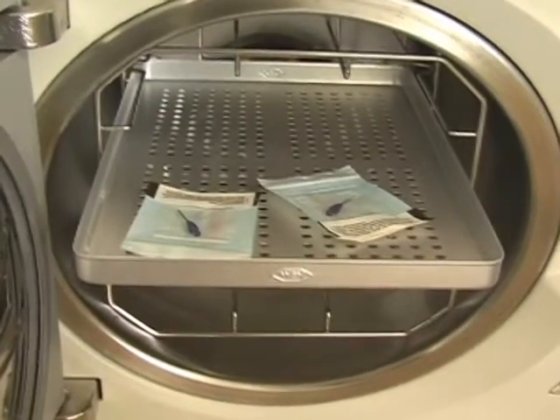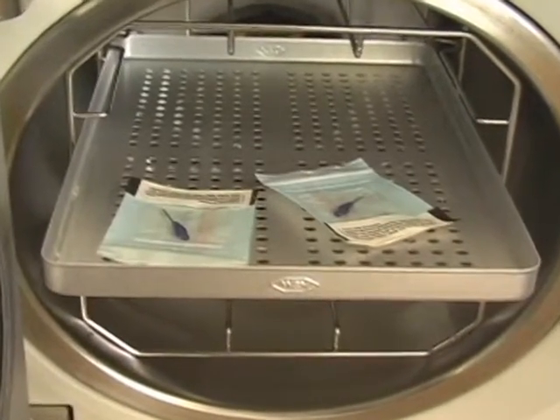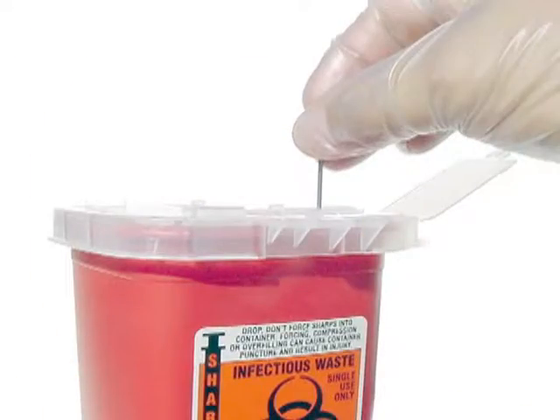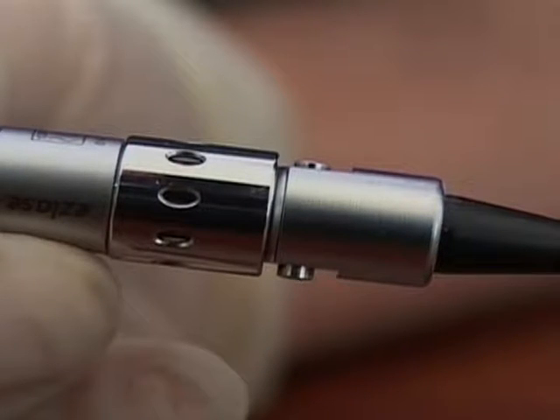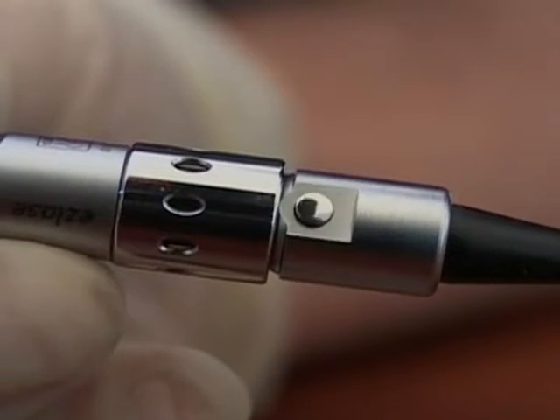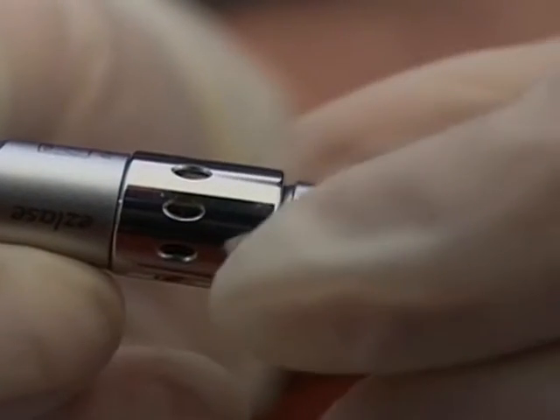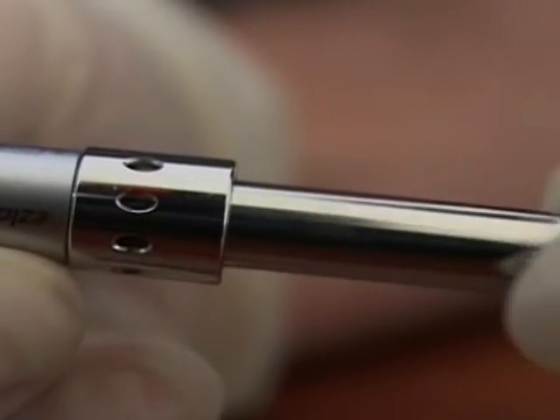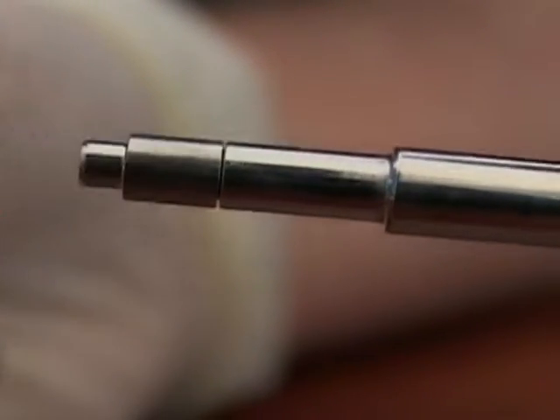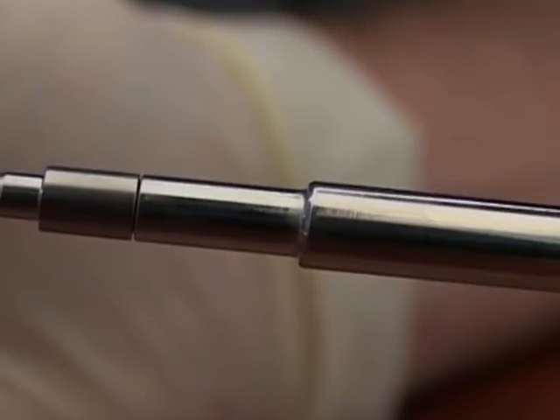Before each procedure, you should sterilize the tips in an autoclave. Remember, it is recommended that each tip be used only once. After each procedure, remove the tip and dispose of it in a sharps container. The handpiece should be thoroughly cleaned and sterilized after every use. To remove the handpiece, depress the 2 buttons on either side of the shaft and simultaneously pull the handpiece off, sliding it off the optical shaft as shown.